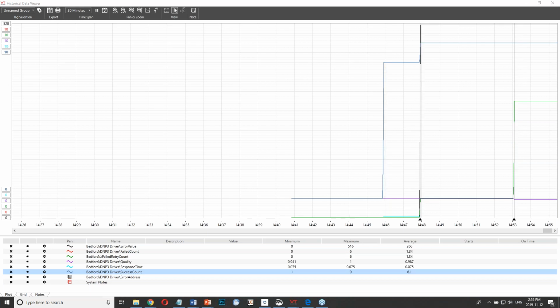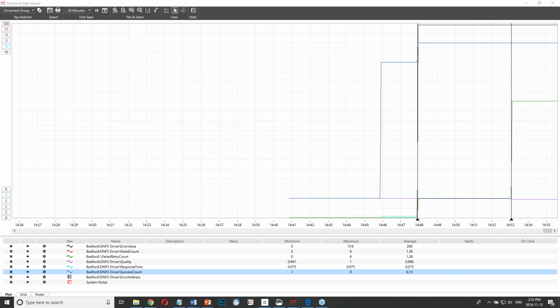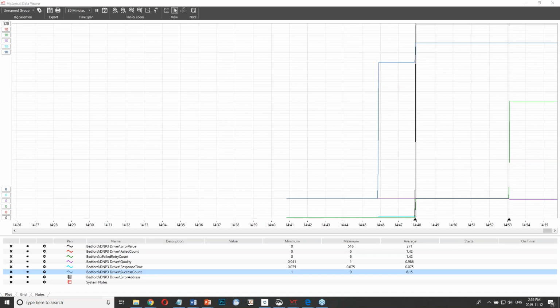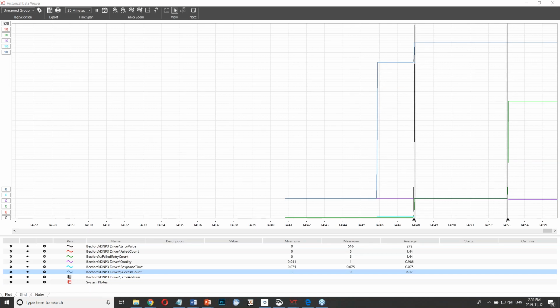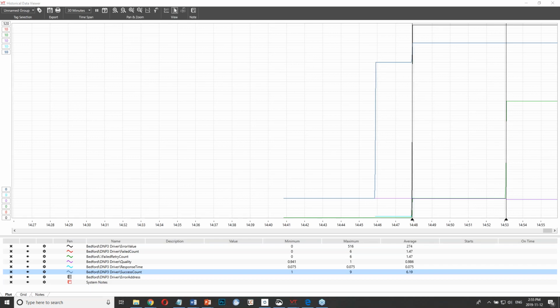One thing to put in as a comment is that the polling queue is for the reads going out, so integrity polls and event polls and things like that. There's actually a separate queue maintained for writes. So if you do try to do a write right in the middle of a whole bunch of reads queued up, it's going to get its turn very quickly so that it's responsive in how it performs. The poll driver does the same thing.